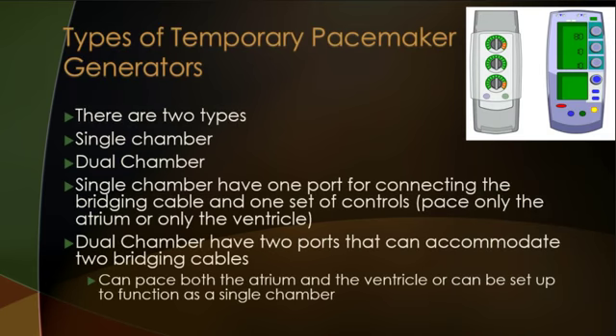There are two types of temporary pacemaker generators. You have a single chamber and dual chamber. Obviously the single chamber, they have one port for connecting the bridging cable and one set of controls. So they will pace only the atrium or only the ventricle, but not both at the same time. Whereas with your dual chamber, you will have two ports that can accommodate two bridging cables, and you can pace both the atrium and the ventricles, or they can be set up to function as a single chamber as well.